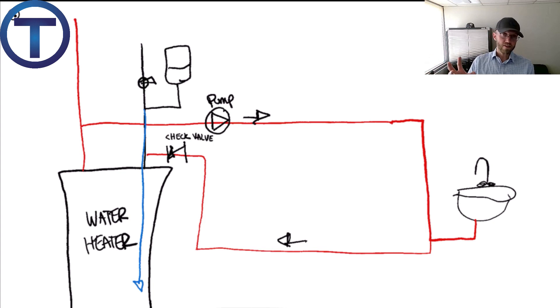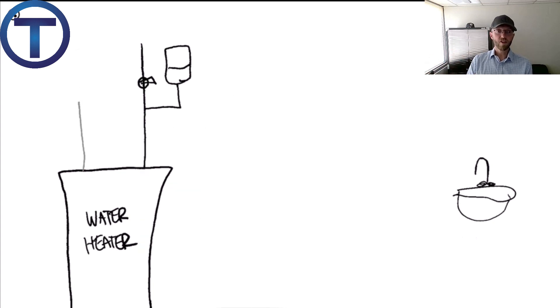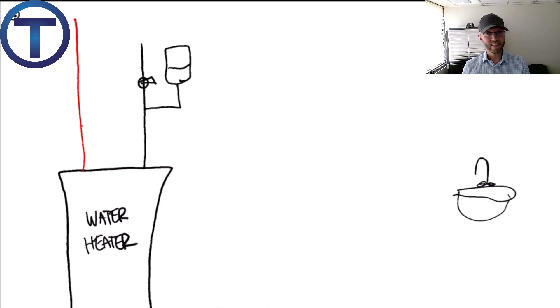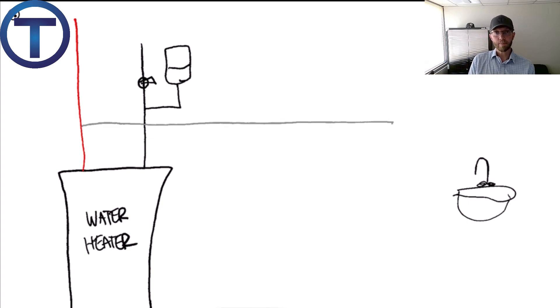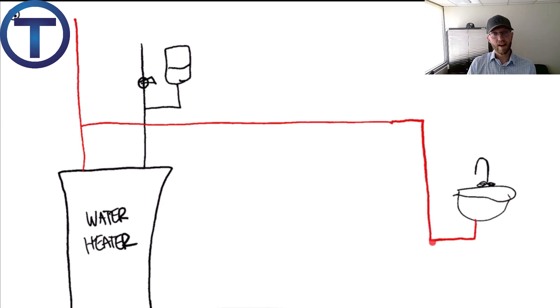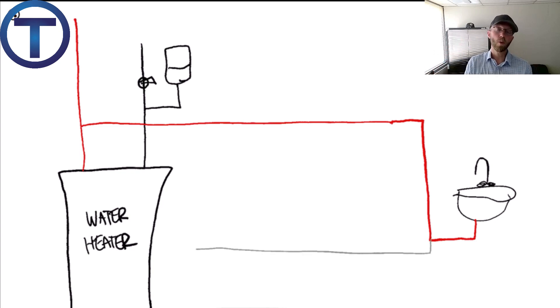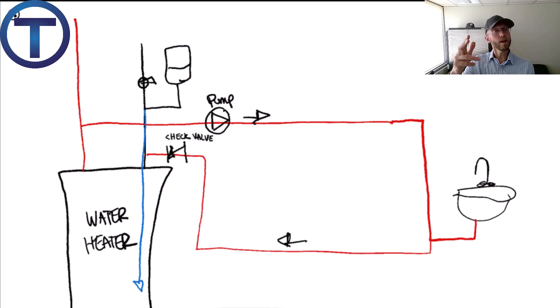In order to have this installed correctly, we must circulate that water in a way that it goes back to the water heater to be heated again. You send that hot water out from the hot side and bring it back to the cold side where it gets pushed through the water heater again to be reheated. It will lose temperature on the way, so we reheat that water.